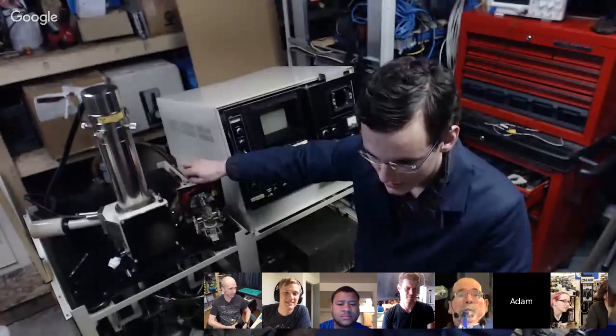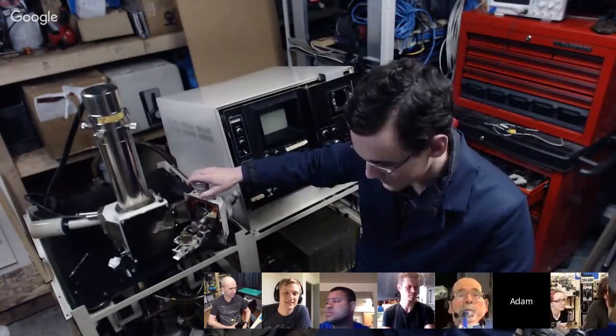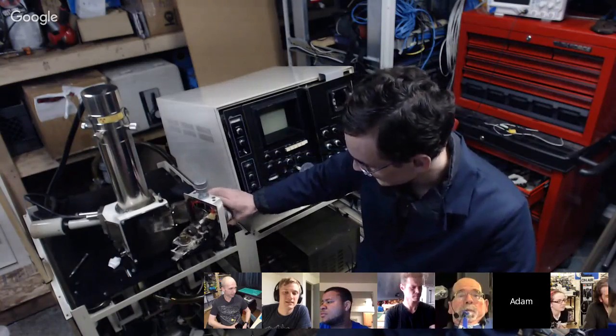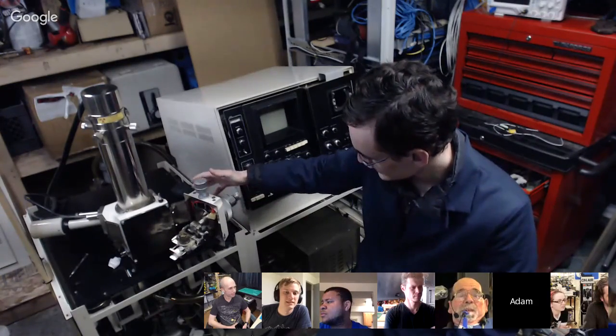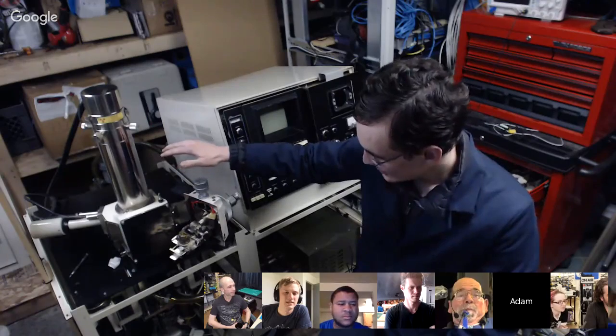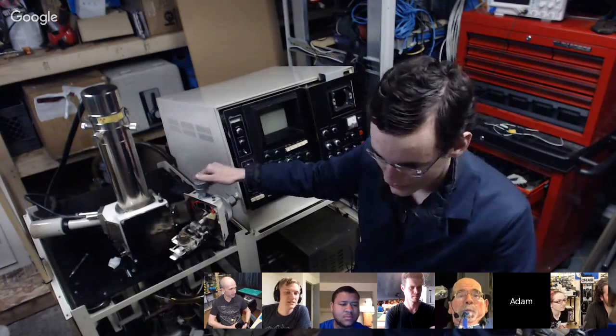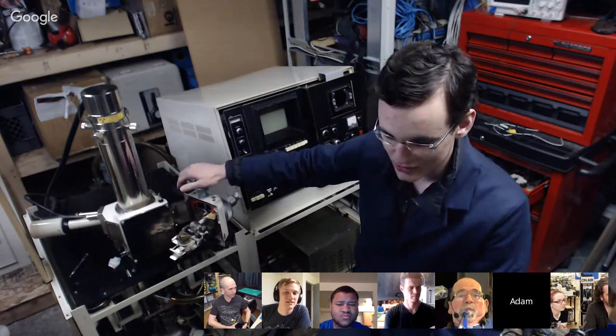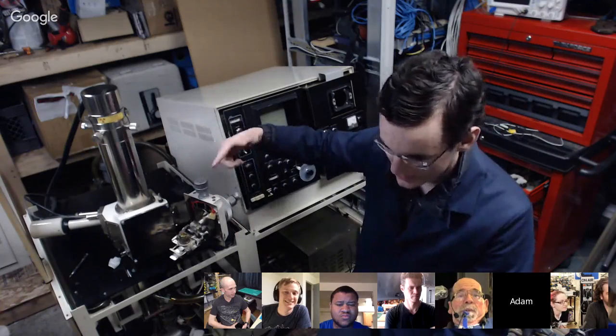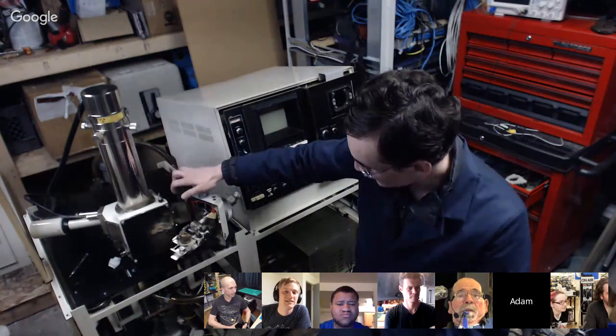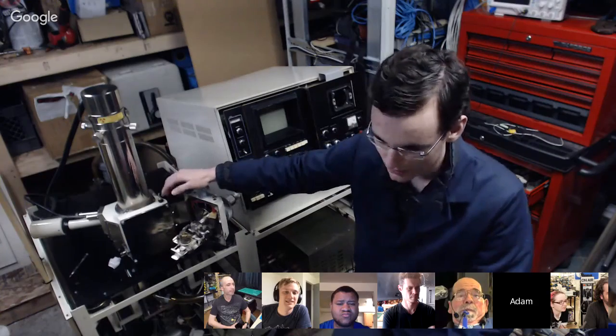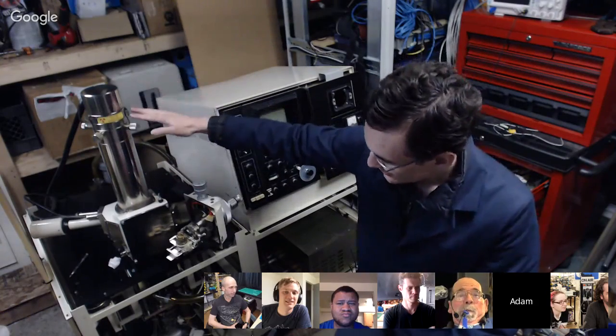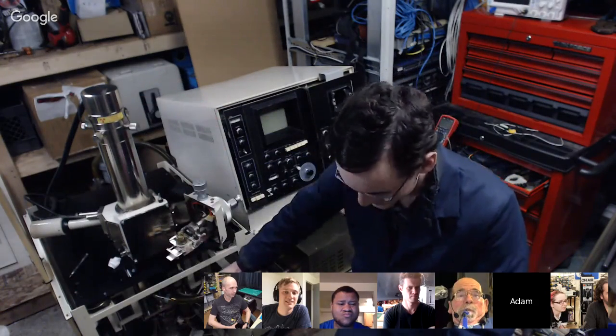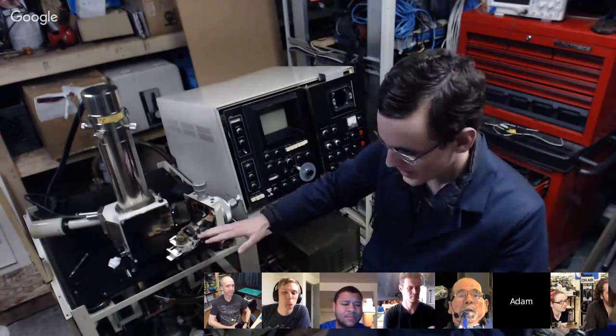It turns out that my microscope's got this really fancy movable stage right here, and this is what allows you to position the sample in the chamber. It's got 5 axes: X, Y, Z, R, and A. And it's all rotary vacuum feed-throughs, which is like the worst thing in the world to do in a vacuum, to make something spin but maintain a perfect seal. So one of the O-rings in this catastrophically failed and vented my column to atmosphere, damaged my filament. It possibly burnt my diffusion pump oil. I don't know yet, but I carried on.